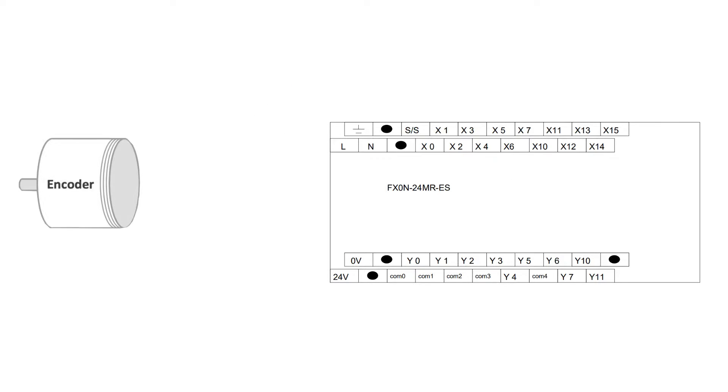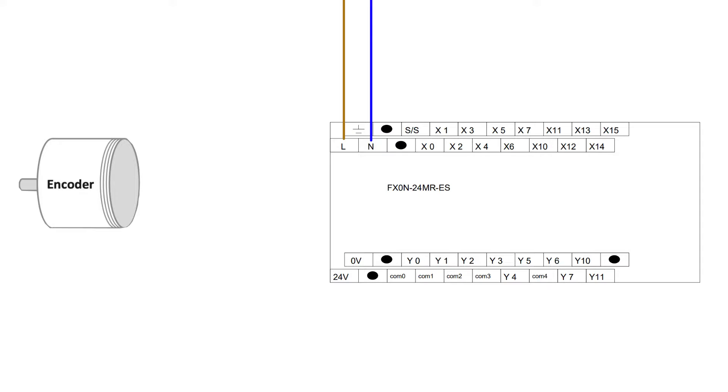Let's first go through the wiring of the encoder. First we will need 230 voltage AC to power up the PLC. Depending if we use PNP or an NPN encoder we will need to either connect 24 plus or zero voltage minus to the S/S terminal.